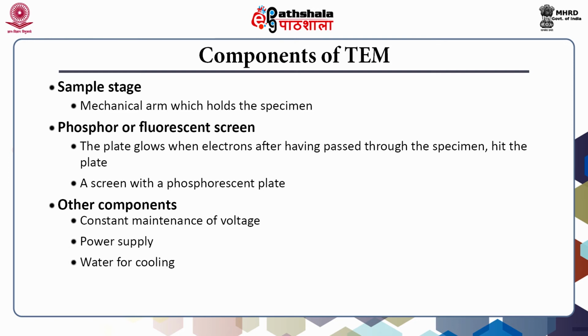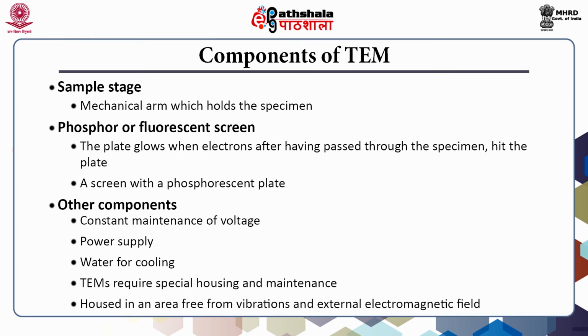Additionally, transmission electron microscope requires constant maintenance of voltage, power supply and water for cooling. Transmission electron microscope is a large instrument and thus requires special housing and maintenance. The equipment is housed in an area that is vibration free and also free from the influence of external electromagnetic field.